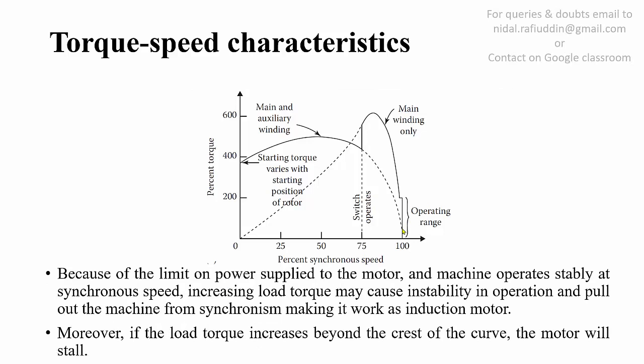At the stable operating point, the load torque can range from zero to about two times the rated value. But as soon as the load increases beyond this, the motor will pull out of synchronism and will operate at a speed less than the synchronous speed, where it will work as an induction motor. Moreover, if the load torque increases beyond the crest of this curve, the motor will stop or stall.